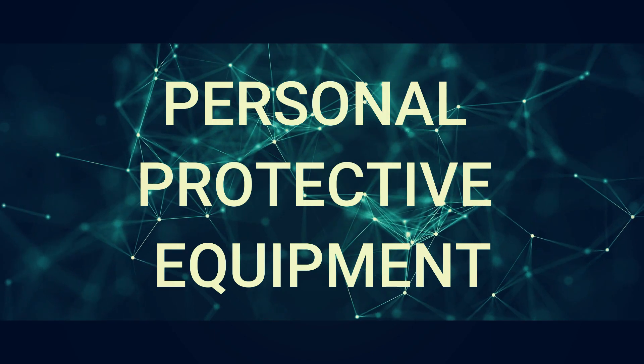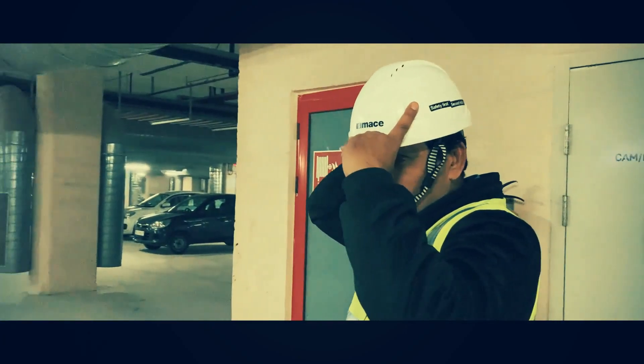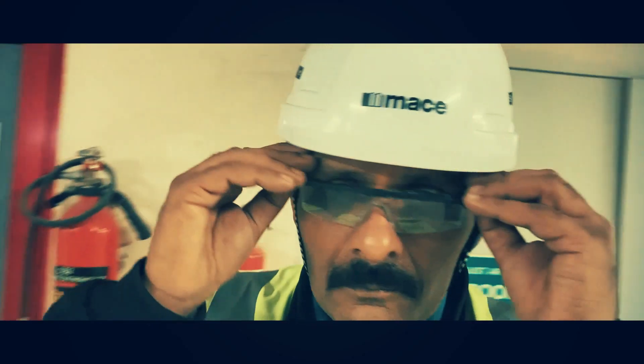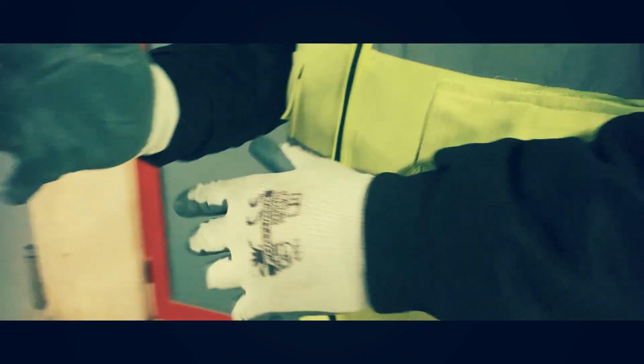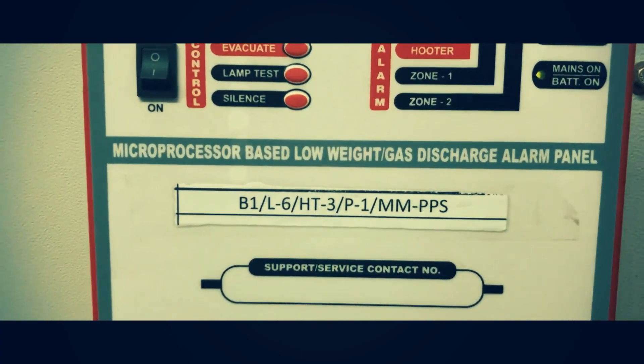Personal protective equipment: Common PPE requirements on job sites include cotton or fire-resistant pants, a cotton or fire-resistant shirt with a minimum 6-inch to full-length sleeve, electric shock-resistant or static dissipative footwear, Type 1 and 2 Class E and G protective headwear, additional high visibility clothing, safety glasses, and work gloves. For electrical workers that conduct their tasks around energized equipment, you should be aware of the standard safety procedures to control the electrical hazards.